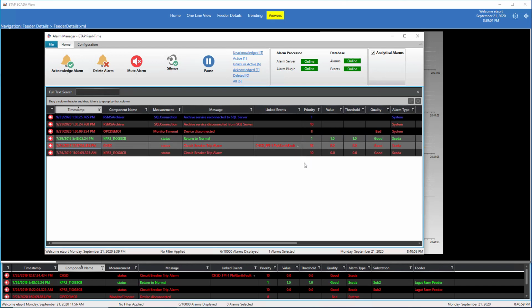So this is where the digital twin model becomes very important and a very unique application in the system, because without the details of the capabilities of transformers, feeder cables, breakers, and so on, we wouldn't be able to create these alarms. So this is a very, very important feature, very unique to ETAP.